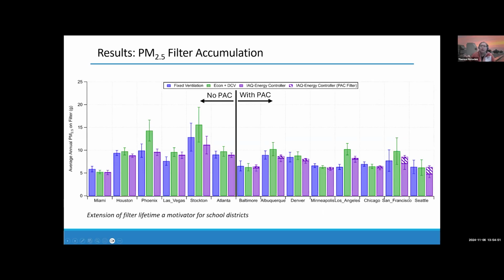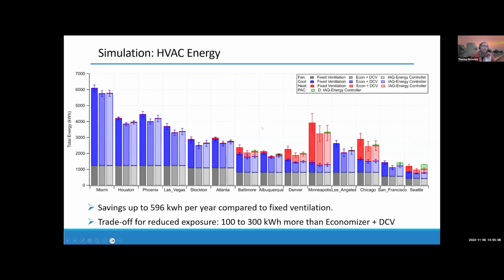If we are bringing in less outdoor air when there's high PM 2.5 outside, we're collecting less particulate matter on our filters, right? And so we also see with the IAQ energy controller a reduction in collection on the filter, and so that will mean an extension of filter lifetime. And finally, in terms of energy, the IAQ energy controller saves energy over a fixed ventilation rate, but uses slightly more energy than an economizer. And that makes sense because there's these hours of the year we would have been economizing, and instead here we prioritize health, right, by not economizing. And so like, for example, in like Los Angeles here, there's a little bit of take back on that cooling energy savings that we've essentially given up in favor of children's health.